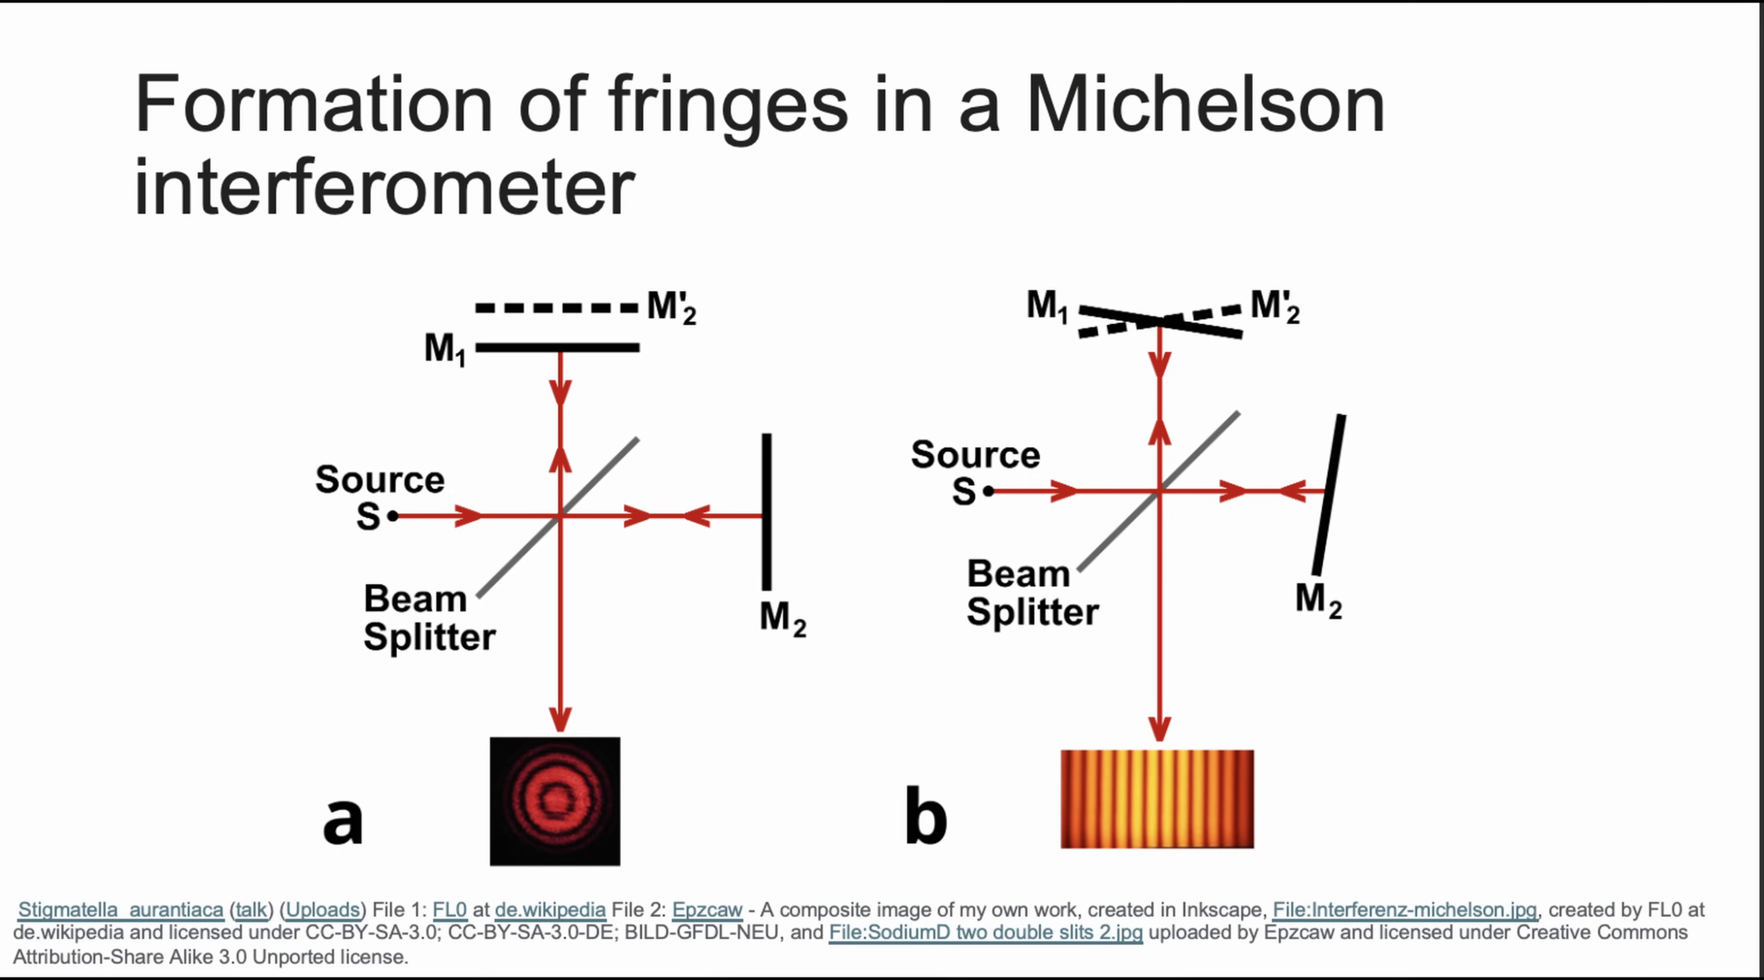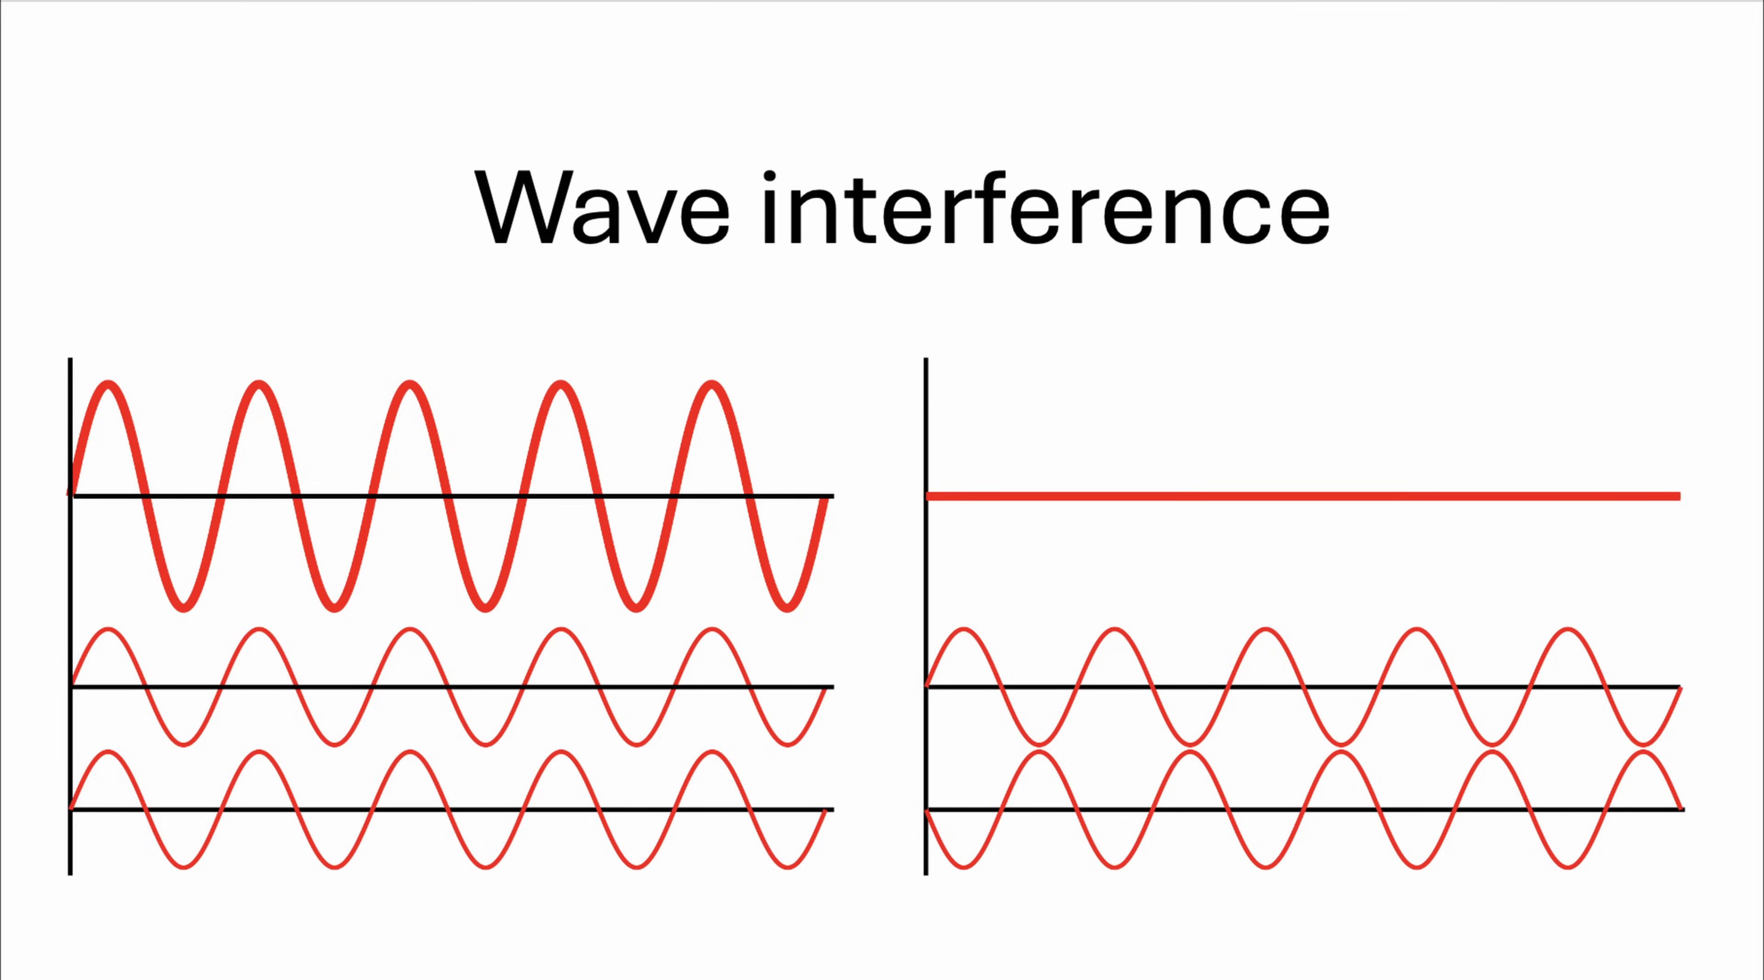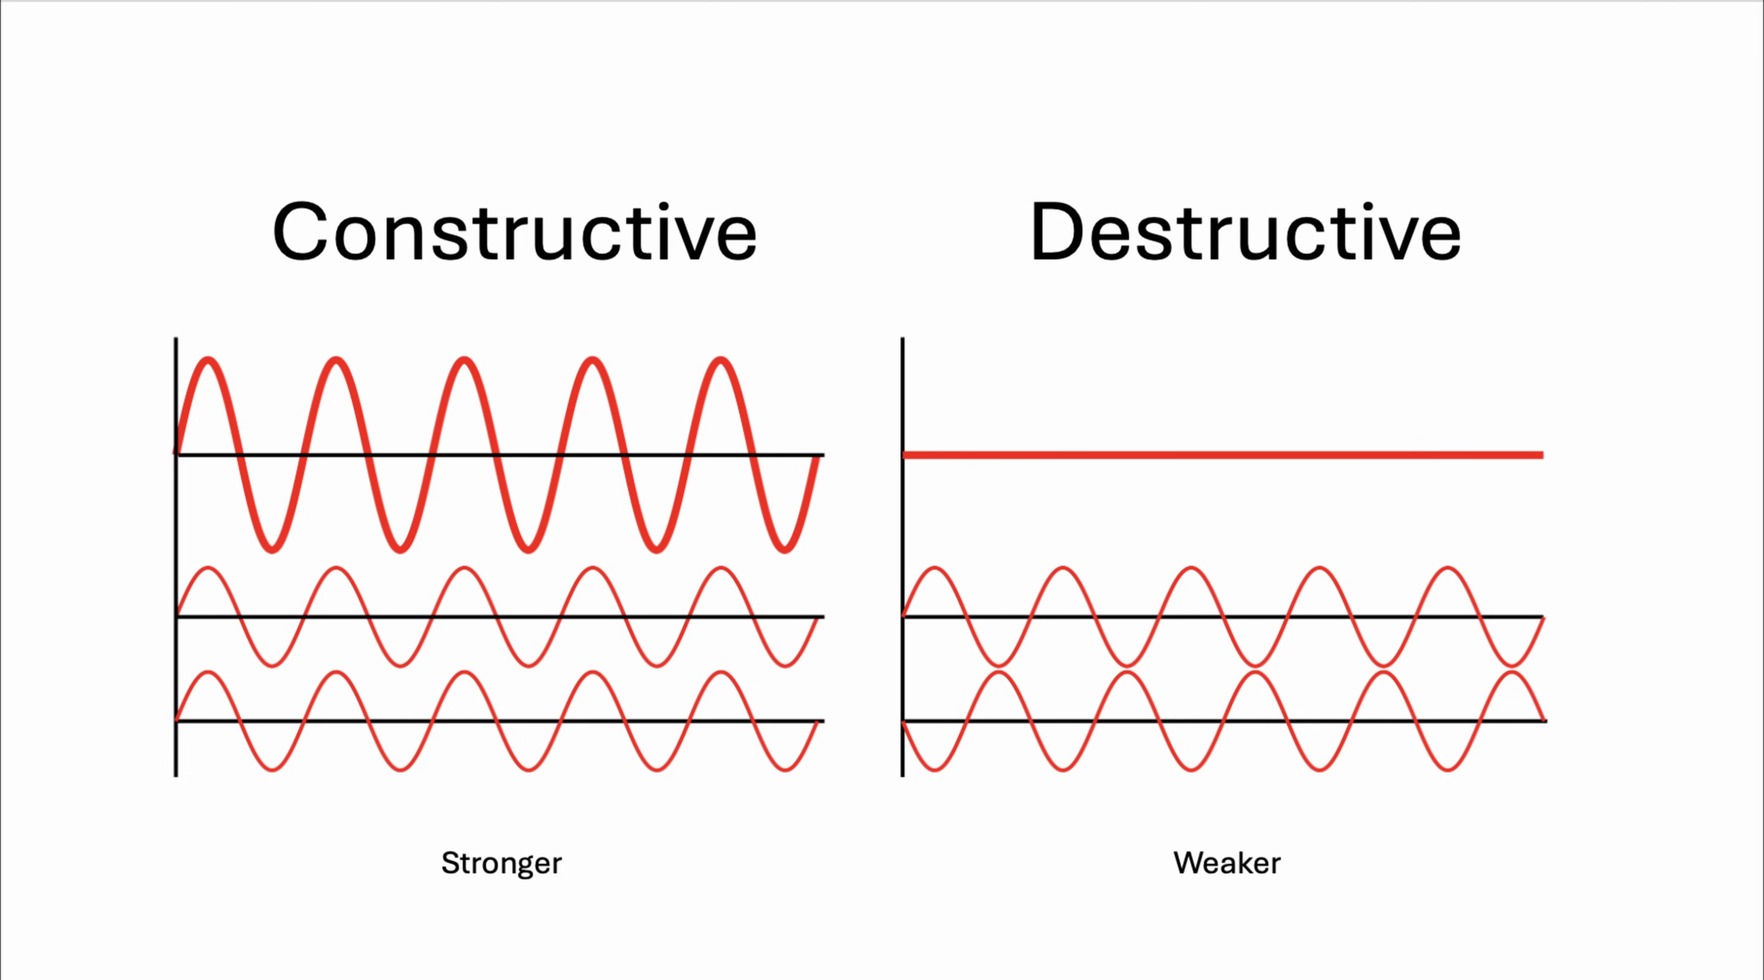Since one mirror is moving and the other is stationary, the two IR beams travel slightly different distances before being reflected back and recombining at the beam splitter. This creates a difference in the path length traveled by each beam. As the mirror moves back and forth, this path difference continuously changes. When the two beams recombine at the beam splitter, they interfere with each other, producing a pattern of constructive and destructive interference.